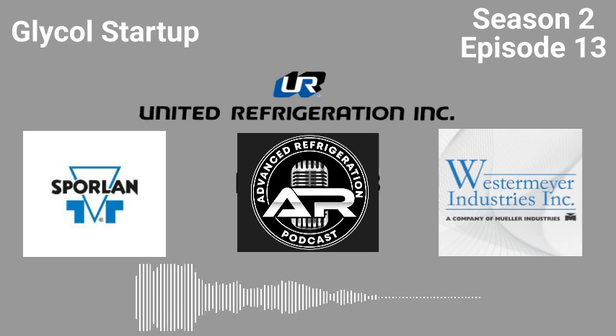So this week, guys, I think we're gonna go over how to do a Glycol Startup and how to bleed air out of systems and some basic Glycol troubleshooting. So we'll dive right on into it, guys. So when doing a Glycol Startup, you've got a couple more things to take into account before you go ahead and do this. You want to get your glycol in there before you start charging the racks. And you want to make sure the glycol system's all ready to go before you start doing anything.